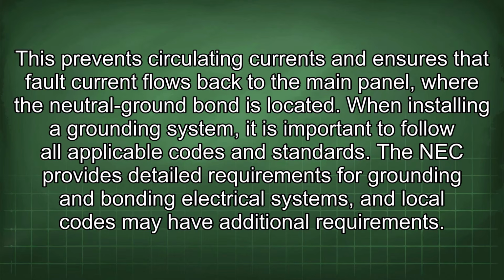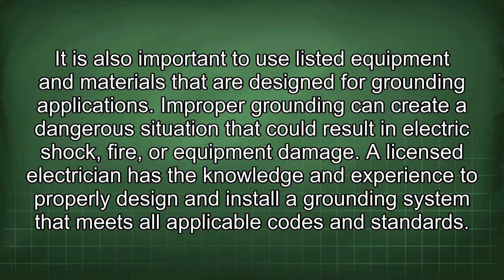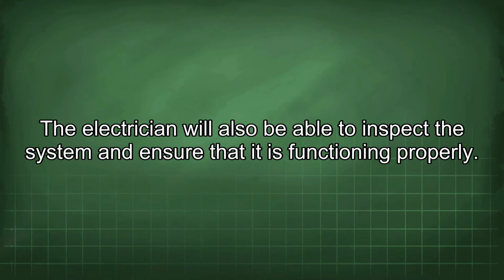The NEC provides detailed requirements for grounding and bonding electrical systems, and local codes may have additional requirements. It is also important to use listed equipment and materials that are designed for grounding applications. Improper grounding can create a dangerous situation that could result in electric shock, fire, or equipment damage. A licensed electrician has the knowledge and experience to properly design and install a grounding system that meets all applicable codes and standards. The electrician will also be able to inspect the system and ensure that it is functioning properly.